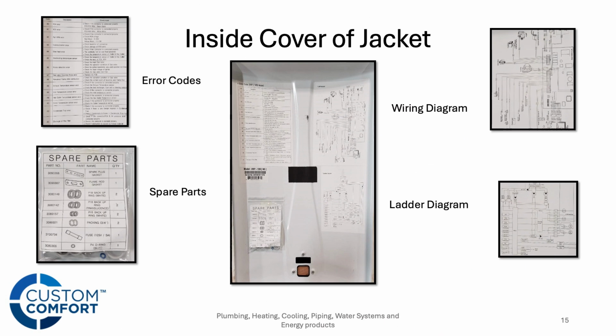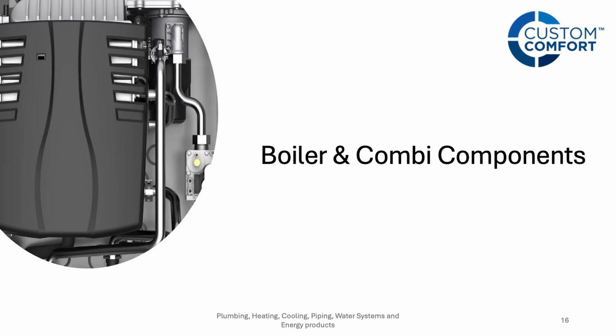Again, looking at the inside of the cover of the front jacket, we're going to give you a breakdown on the error codes, a wiring diagram, a ladder diagram, and then a bunch of spare parts as well, right? So you've got gaskets, you've got a couple spare fuses. Let's say you've got some bad power on the install, you blow a fuse, you're not dead in the water. You got a spare fuse there. It's also where you're going to find the propane conversion kit, in that spare parts bag on the inside of the jacket.